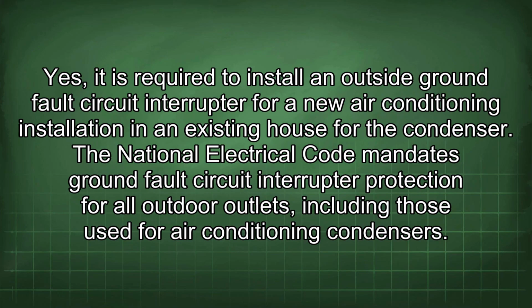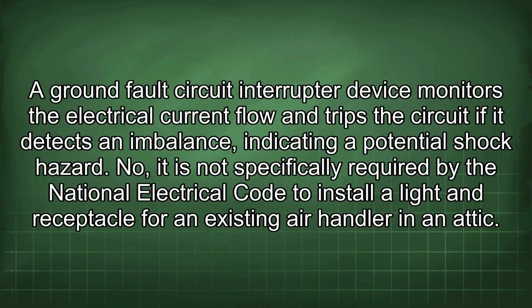Yes, it is required to install an outside ground fault circuit interrupter for a new air conditioning installation in an existing house for the condenser. The National Electrical Code mandates ground fault circuit interrupter protection for all outdoor outlets, including those used for air conditioning condensers. A ground fault circuit interrupter device monitors the electrical current flow and trips the circuit if it detects an imbalance, indicating a potential shock hazard.